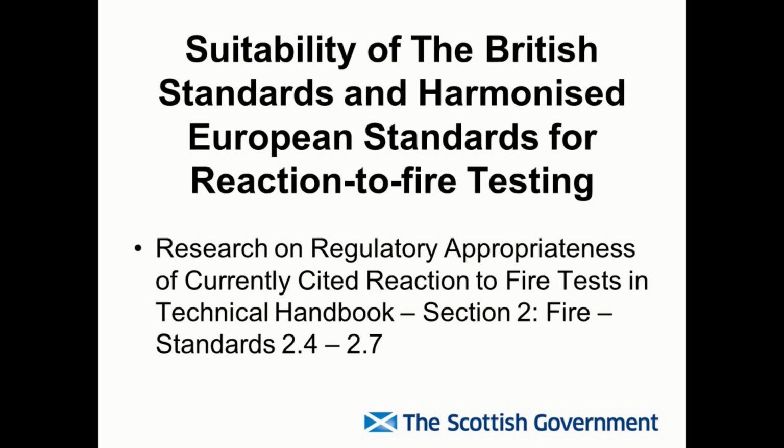It was deemed important to understand the role of standardised fire test methods, in particular reaction to fire test methods, in assessing the fire safety performance of building materials, systems and components for buildings in Scotland for regulatory compliance with the standards. In this report, a standardised fire test method was defined as a description of a methodology, apparatus and associated test parameters that are used for assessing one or more attributes of fire performance of a material, component, system or assembly for the purpose of defining a common benchmark or benchmarks for performance, which can be uniformly applied to a wide range of products using equivalently designed and functioning apparatus by different people in different laboratories or facilities with a tolerable level of variability.